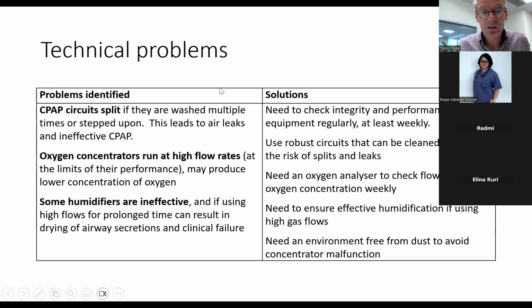There are some technical problems you can run into when you're giving CPAP, and I just wanted to run through a few of those and the solutions for them, because in using CPAP in many studies, we've found lots of different problems can arise, and there are solutions. So sometimes the circuits split if you wash them multiple times, or they're washed in too heavy bleach, and that can lead to air leaks along the circuit. And if you have an air leak in a CPAP circuit, then it won't deliver CPAP. So you need to check the circuits regularly and make sure people don't step on them, so that they split.